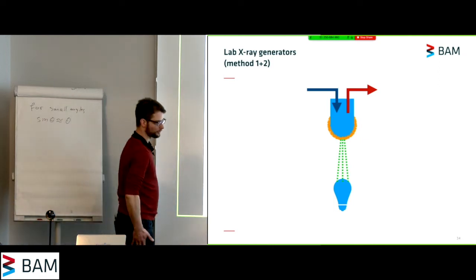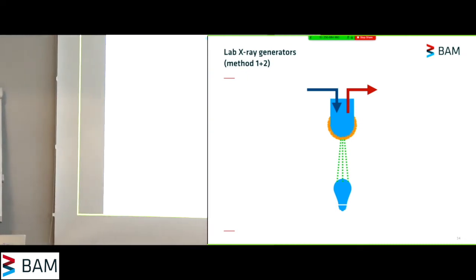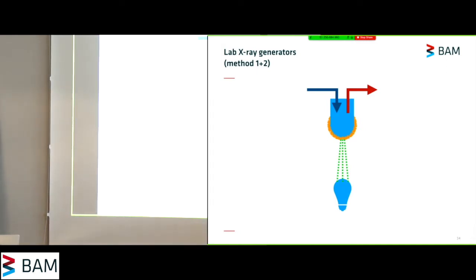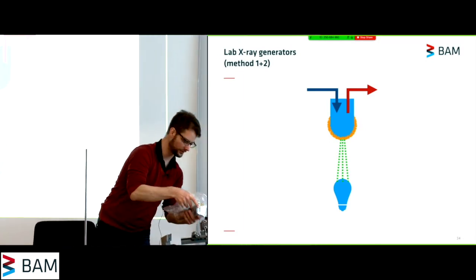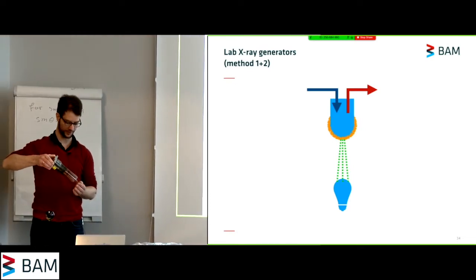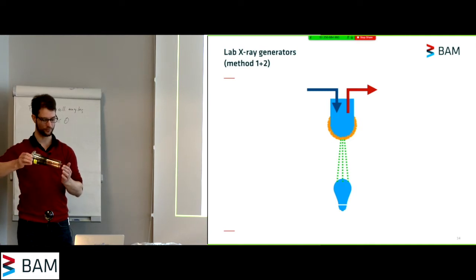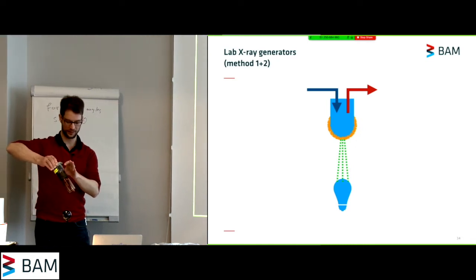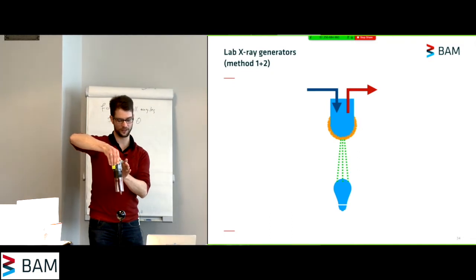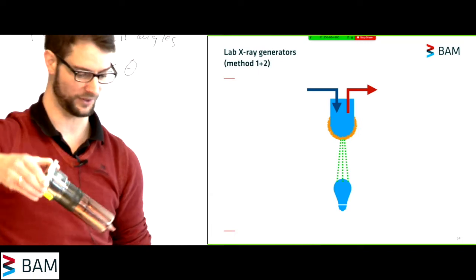So, in the lab, one of the most common X-ray generators you will see is still using the Coolidge tube. And I've got one here. I don't know whether people online can see it. But this is one of the X-ray tubes from our X-ray generator. I'll have to be a little bit careful here because it is essentially a vacuum tube. I hope this is visible on one of the camera streams. So it is a vacuum tube, a glass vacuum tube, which contains a cathode on the inside and an anode.